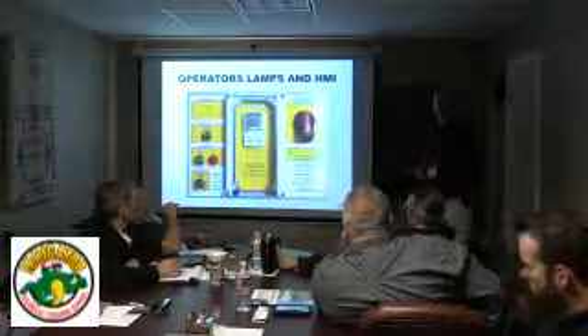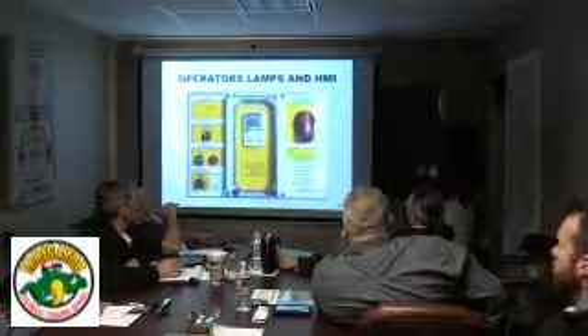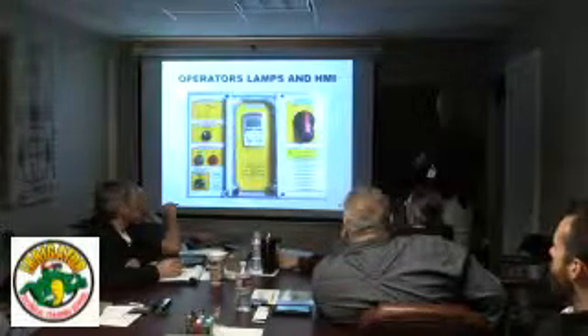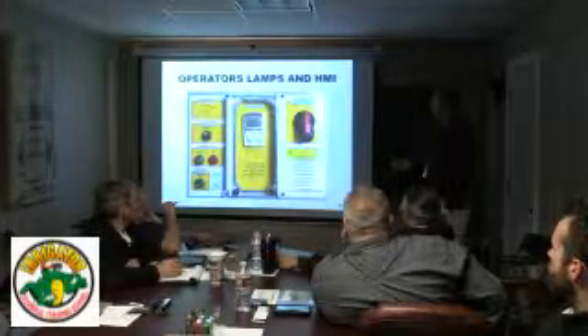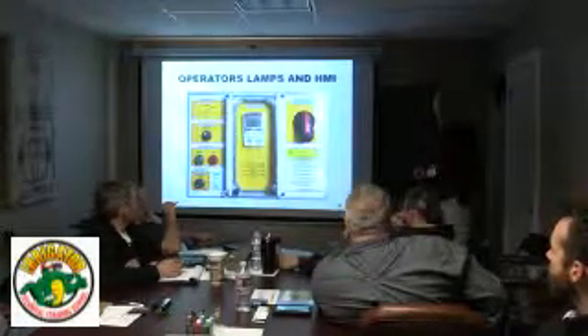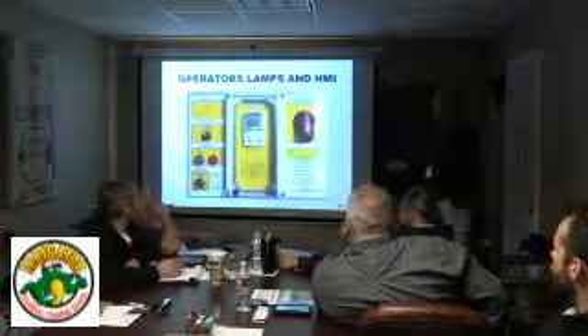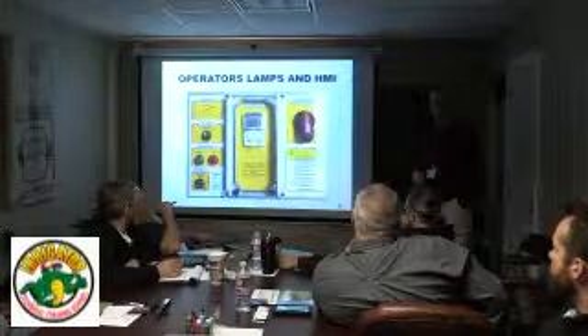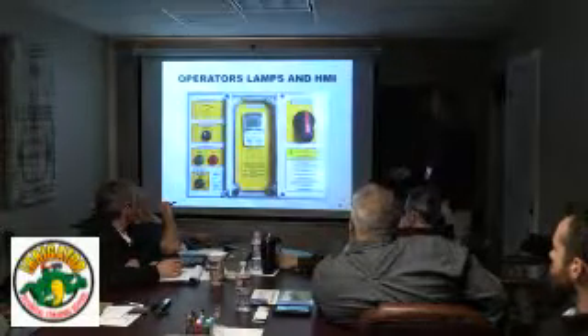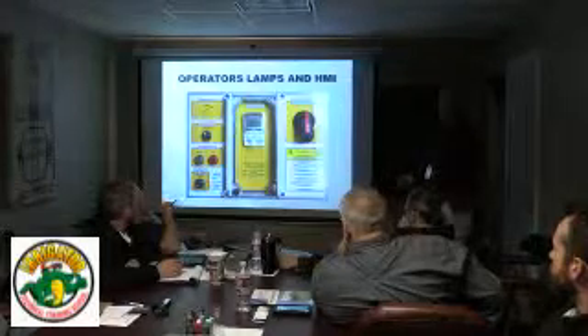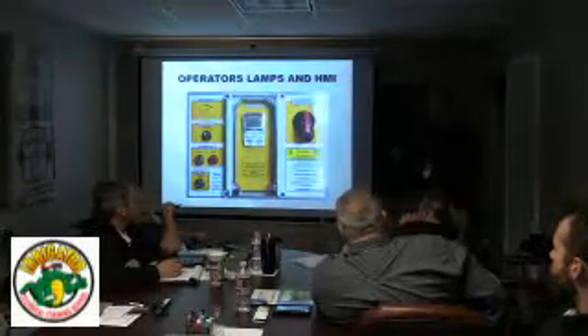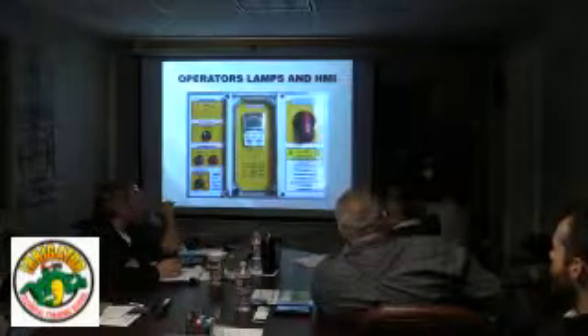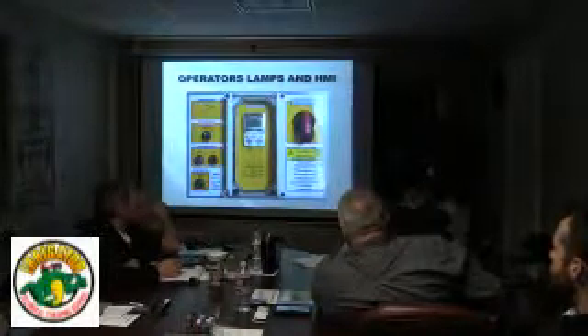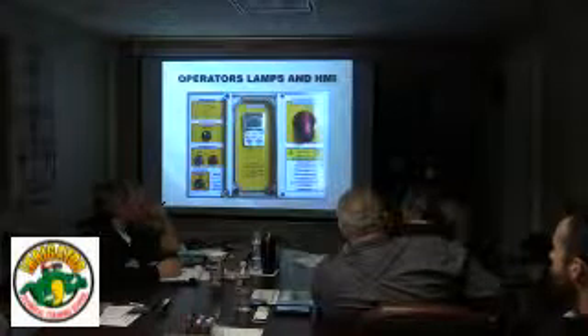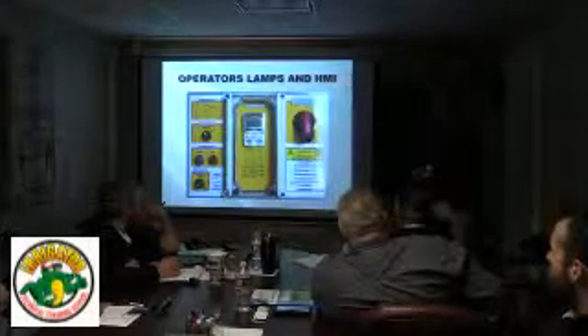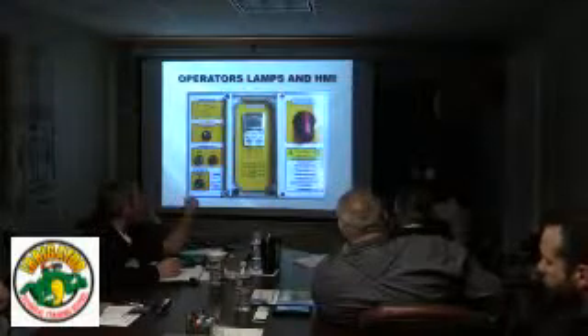Another thing to keep in mind is that because most motor manufacturers recommend a minimum speed, we will program in the drive a minimum frequency of 30 hertz. So when you turn this to hand, the drive's going to automatically go right to 30 hertz, regardless of where this is at. If it's anywhere below 30, it's going to go right to 30. And then once you start to turn it up, it won't speed up until you get above 30. Once you get above 30, then you'll be able to adjust it from 30 to 60. But just keep in mind that as soon as you go to hand, it's going to go to 30 hertz regardless.